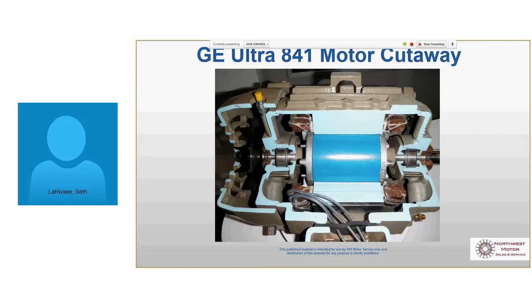These normally have open bearings on them. These are regreasable. They're open on the outboard side and shielded on the inboard side. So again, to facilitate that grease path, but not get grease back into the motor.